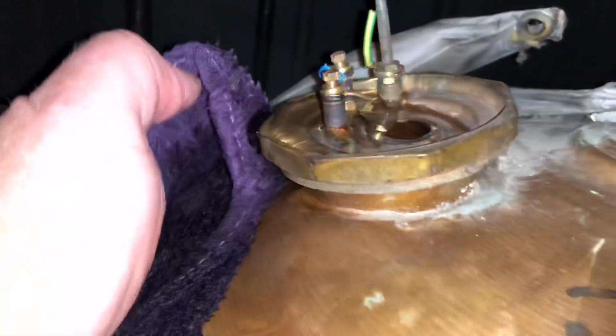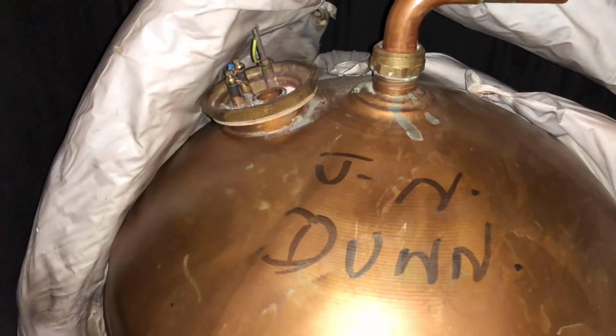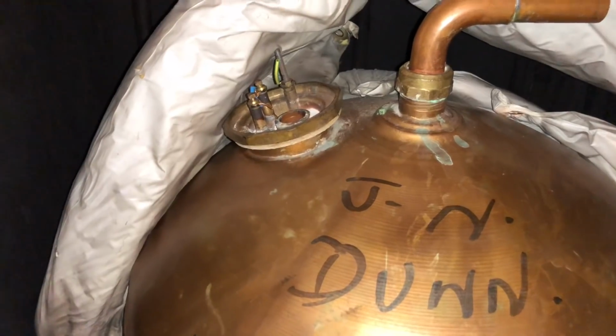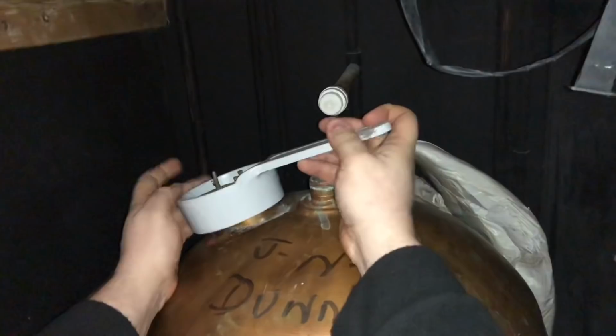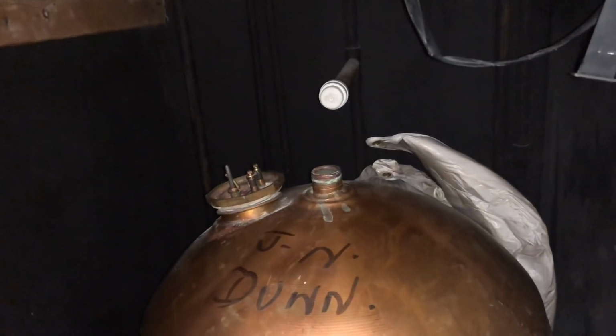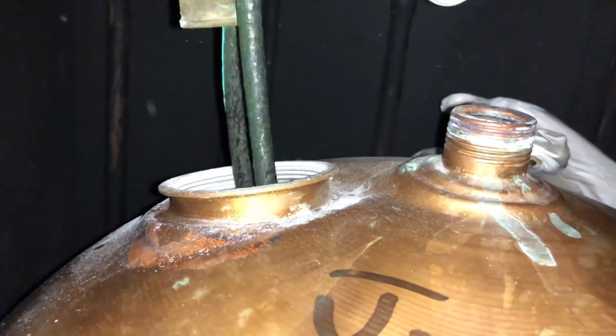We've drained the cylinder down now, still just a little bit of water in it, and now we need to take the immersion heater out. And this immersion heater is very stiff. It's been in a long time. So what we've done is we've heated it up with the blow lamp. I don't actually normally use my blow lamp anymore, but we've heated it up so that we can get it out, and then we've managed to get it out. It's actually bent, and it's difficult to get out of the cylinder now. But I'll just show you this immersion heater. It's in a right old state.